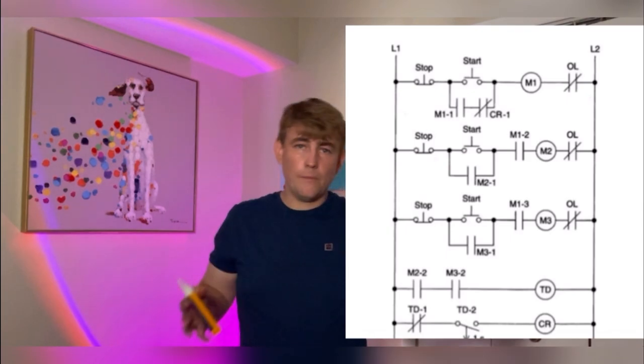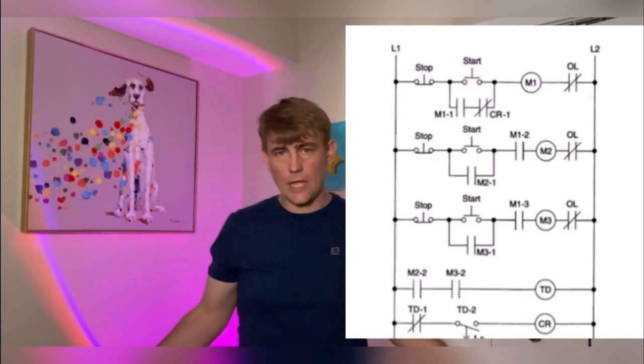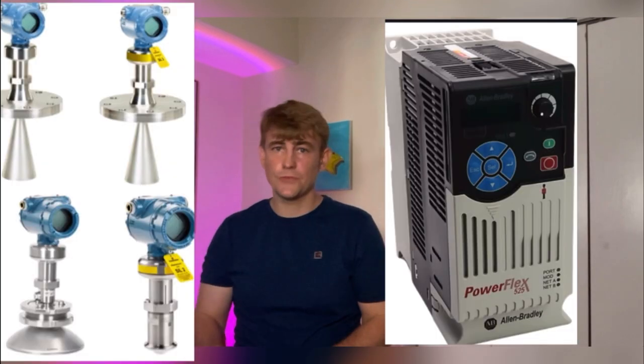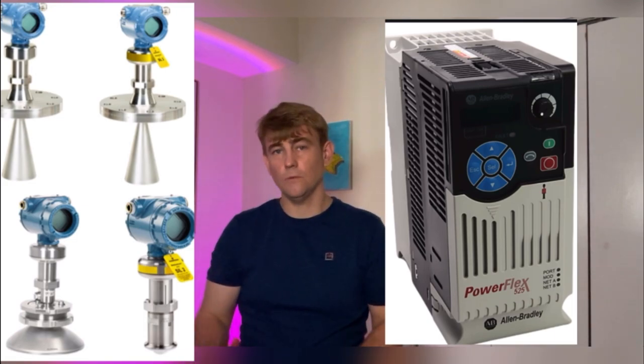You can start getting into multi-million-dollar systems, things that are using a $100,000 motor. Then at that point, you're going to see things like variable frequency drives and level sensors. Say this pumping station uses a $50,000 pump, and we don't want to turn it on and off. We want to reduce the number of times we turn it on and off. Maybe we have a level sensor that gives us an exact level, and then that will be converted through a PID controller to a speed output, and we'll control the speed. And rather than turning it on and off, maybe we'll just keep the level right around a certain area, so we can control the number of startups.